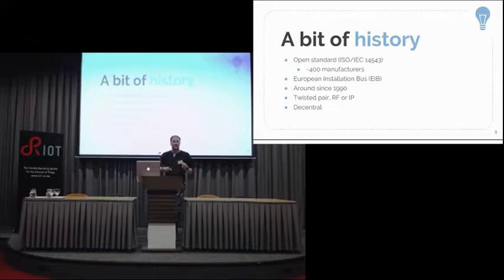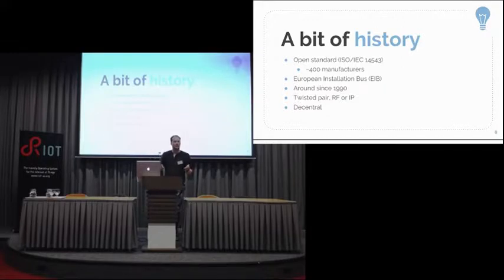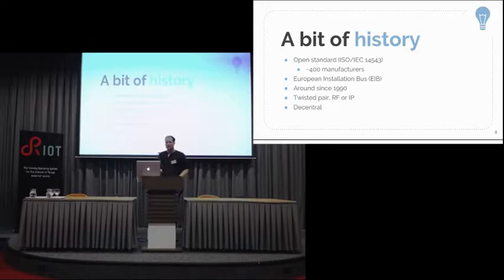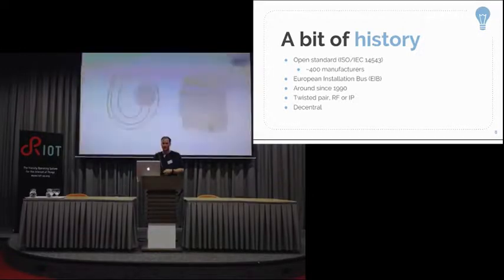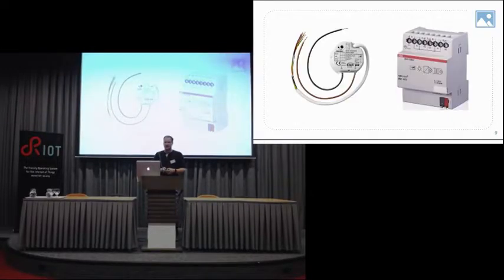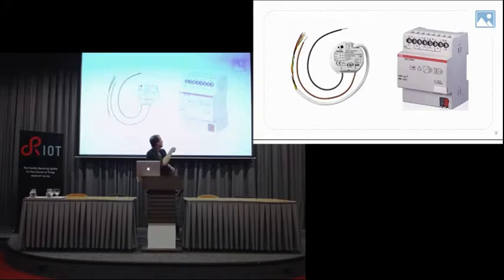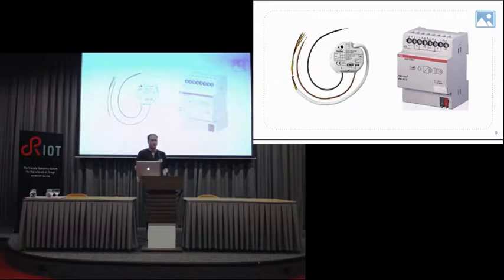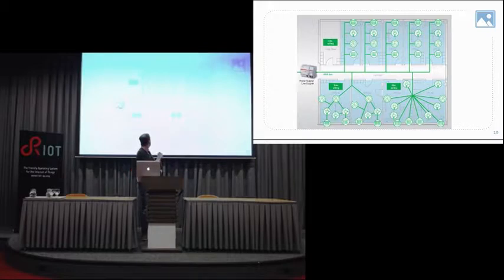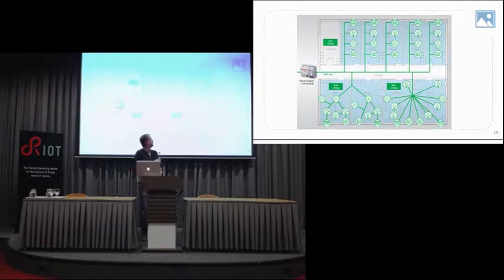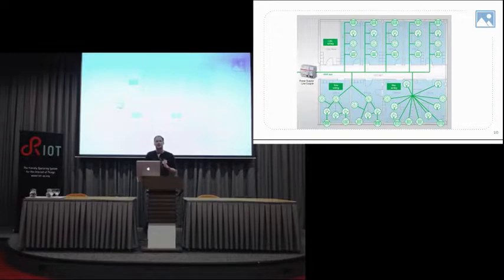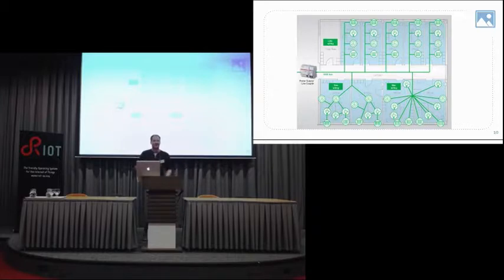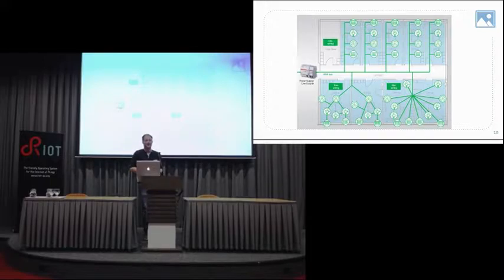If I toggle a light switch, it will send the commands to the light bulb to go on or off, not having some central system in place which runs some home automation software that will do the routing. Whenever some component fails, the whole network should just work. The typical devices are like you see on the picture - you have the things that you integrate in your wall socket, but you also have the more robust versions which go into your utility closet. Basically all the switching goes from there. The KNX network can have different topologies - you can have tree wiring, star wiring, or maybe do it the neat way and have a line wiring version. I guess my house is a mix of all of them. I didn't put down the cables, they were installed, so I think that shows the easy way.